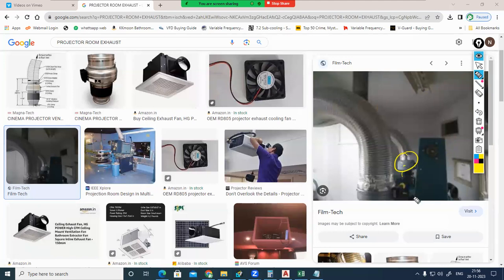So if the movie projector has a fan, that fan will not have that much ESP, external static pressure, to deliver the air to a larger extent. Static pressure, we can study. That's why, if you have an exhaust fan ejecting the heat generated within the space to the outside, then a lot of heat you can neglect. By that scenario, how much heat rejection has to be considered? Negligible only, most of the time.